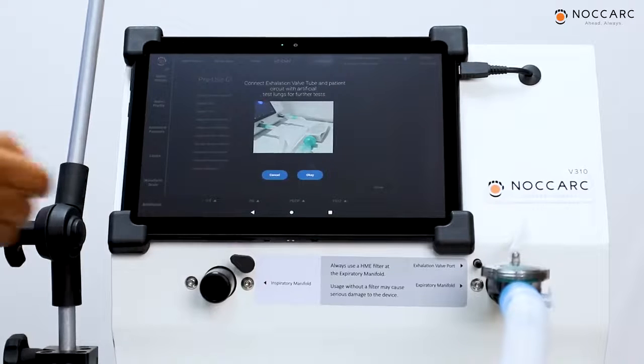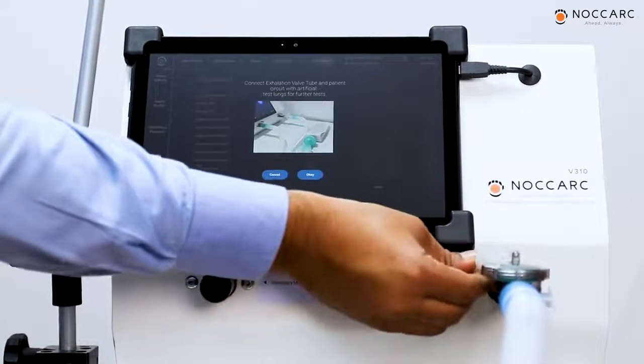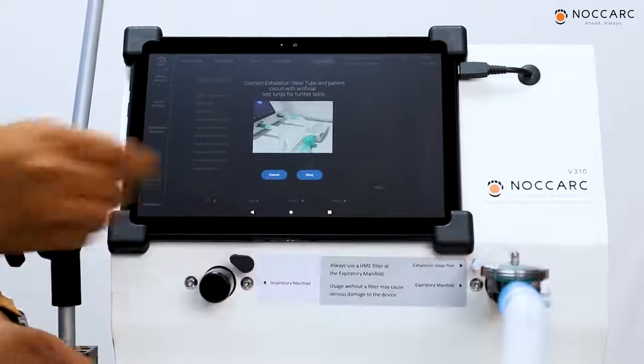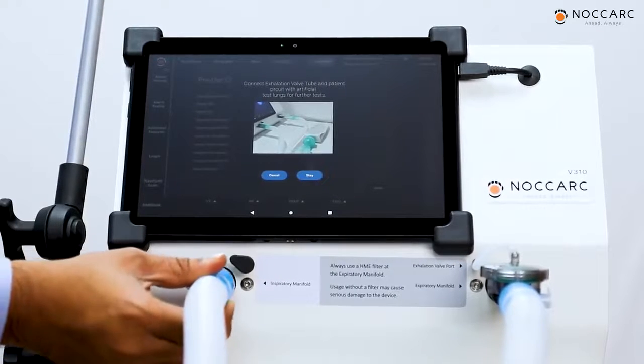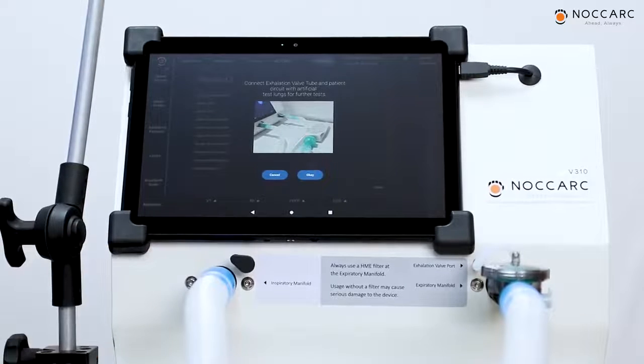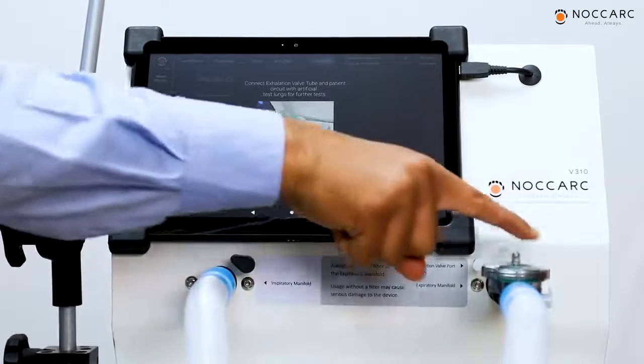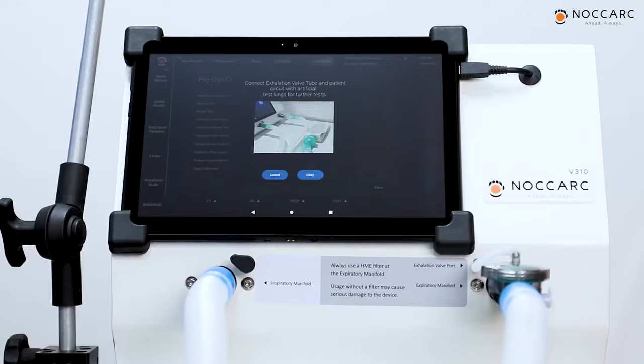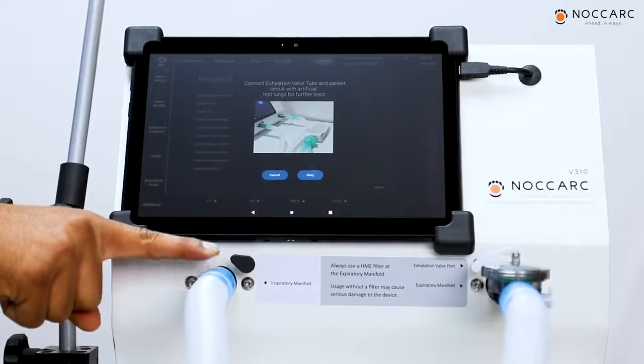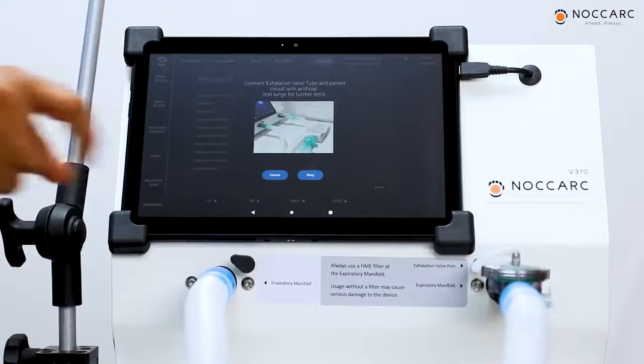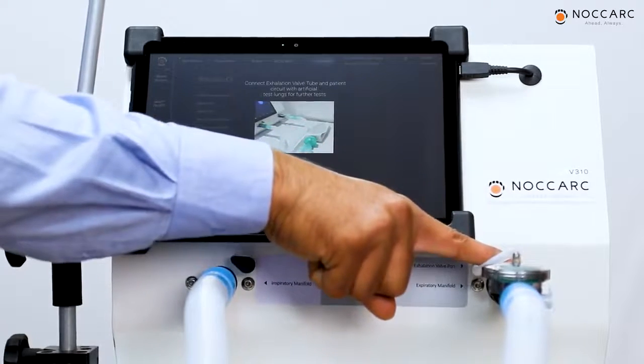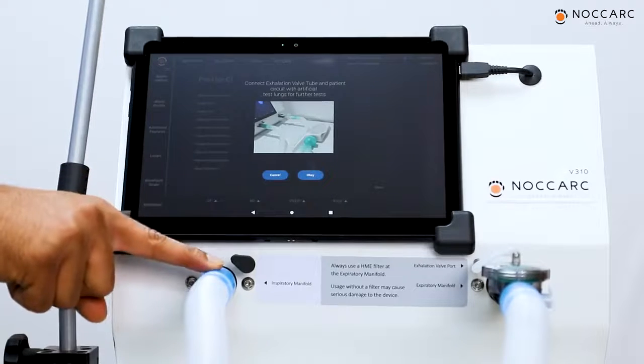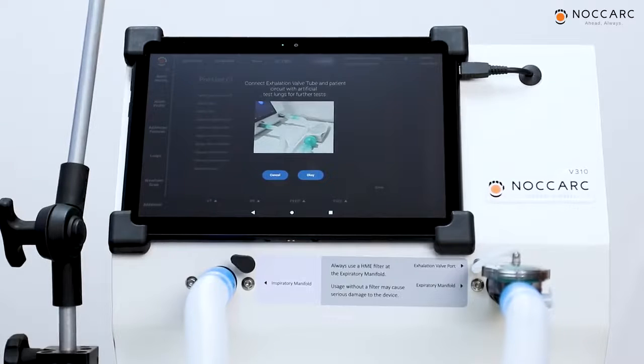Now we have to connect the exhalation valve port tube to this exhalation tube port, and similarly connect the tube to the inspiratory port. Before performing the next test, we have to ensure that from inspiratory port to expiratory port there should be no leakage. If leakage is present in the circuit, then the sensor calibration test may fail. So we have to always ensure that there is a closed loop between inspiratory and expiratory port. So I have connected tubing to inspiratory, then I have connected the test lung, and I have connected the active exhalation valve to the expiratory port. Means closed loop between inspiratory and expiratory is fulfilled. So I will press OK.